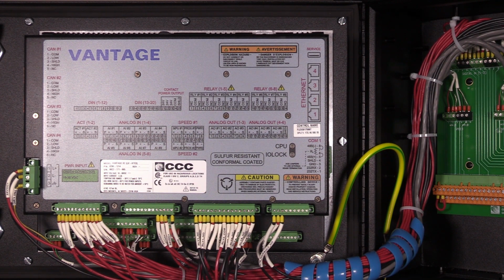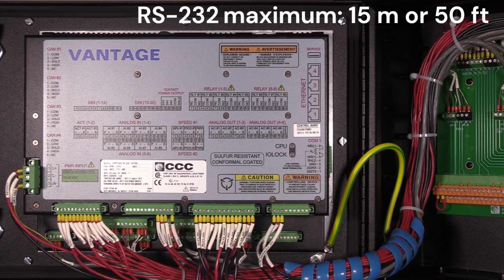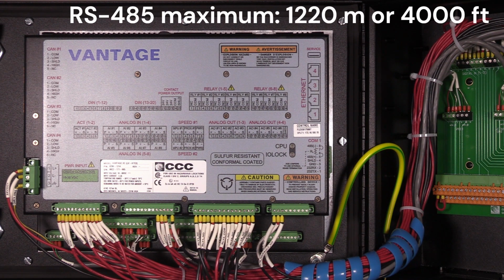The serial connections have the following specifications. A shielded cable is required when using this port. Maximum distance for the RS-232 is 15 meters or 50 feet. The maximum distance for the RS-485 is 1220 meters or 4,000 feet.